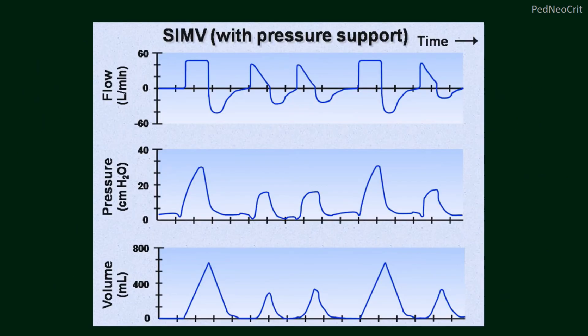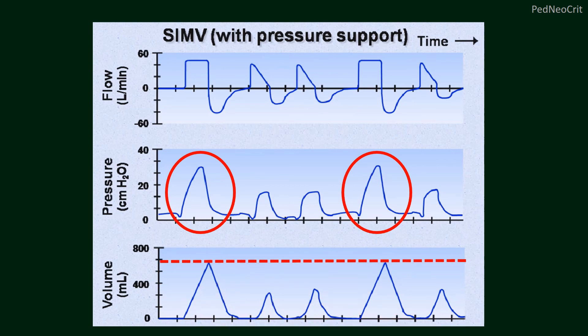These are the waveforms in SIMV mode — flow waveform, pressure waveform, and at bottom, volume waveform. The mandatory breaths provide a good amount of tidal volume, almost 700 ml. But in between these mandatory breaths, there are the patient's spontaneous efforts and pressure-supported breaths, in which the patient receives less tidal volume — less than 400 ml. So SIMV is actually a mix of mandatory breaths and spontaneous breaths.